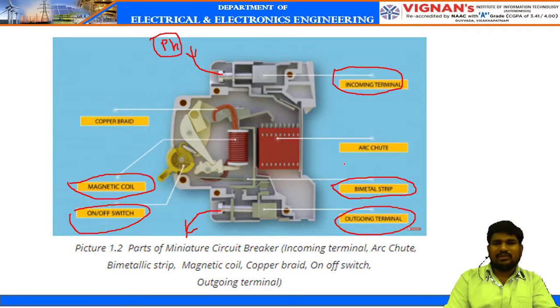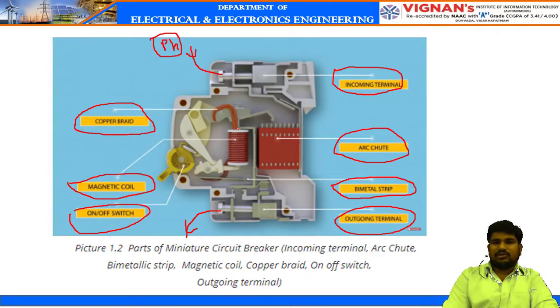During on-off conditions, there may also be a chance of an arc occurring. To quench this arc, the arc chute is useful. We have seen the arc chute in air brake and air blast circuit breakers. Similarly, here the arc chute is used to quench the arc whenever switching occurs. One more part is the copper braid, which is used to connect the circuit and the magnetic coil. So these are the construction parts of an MCB.